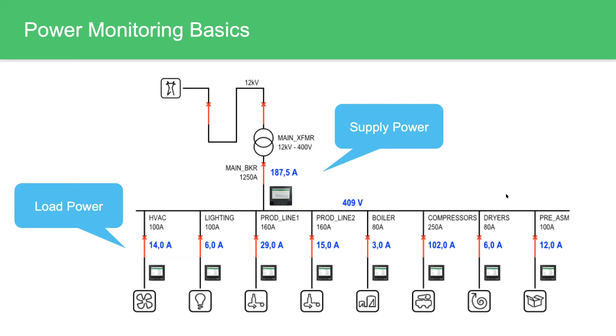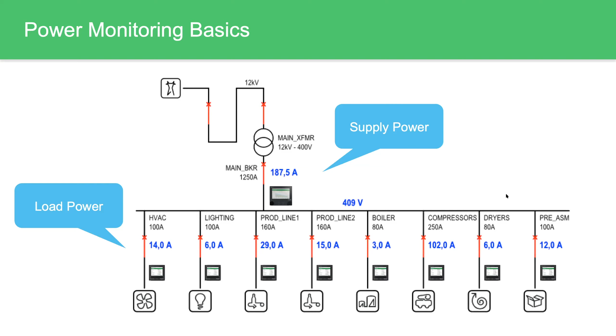These meters are installed in key locations throughout the electrical distribution system. Probably the most important location is at the main incoming breaker, for monitoring the quality of power supplied to the facility from the utility and measuring the total energy the facility uses. We'll also see meters installed in downstream switchgear and distribution panels, monitoring power delivered to all the different equipment and loads in the facility. In this basic example, the meters are monitoring loads from HVAC equipment to compressors and other manufacturing equipment. Data from all these metering points is used for monitoring system health and efficiency, capacity management, equipment monitoring, and power event analysis.